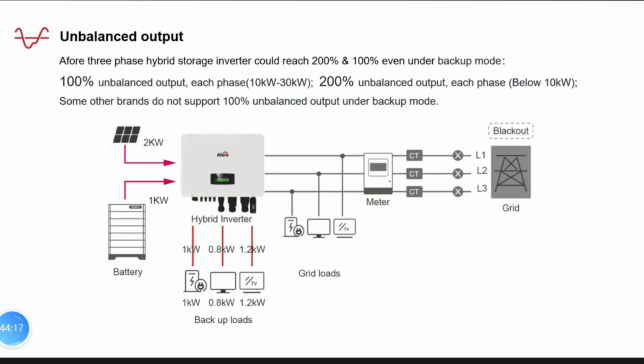So this is the example or detailed information for the unbalanced output. From this picture, we see the numbers deliver a little bit more smoothly. We mentioned for the models below 10K and included, the EPS output can be achieved 200%. That means each phase line, for example, for L1, 10K, it can deliver 6.6K energy, and the other two lines keep zero. And under these extreme conditions, the inverter still works. For these models from 12K up to 30, this part can deliver 100% unbalanced load.